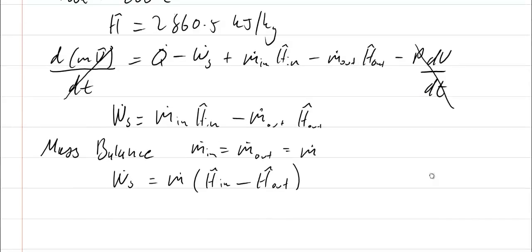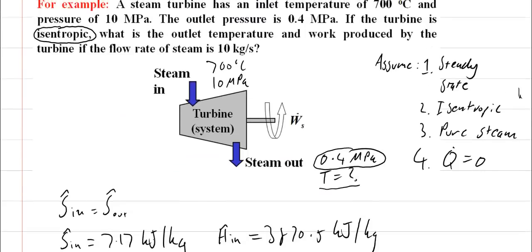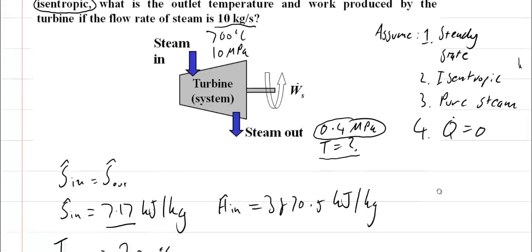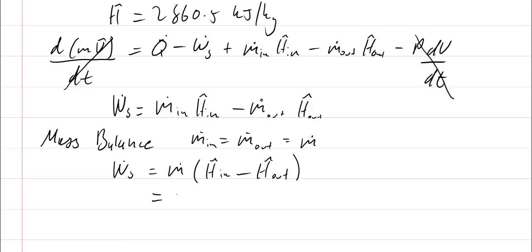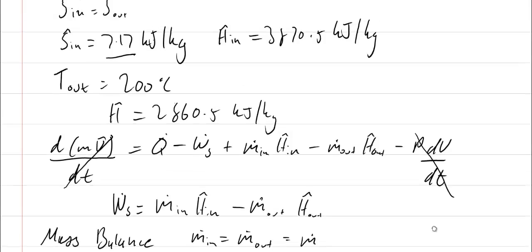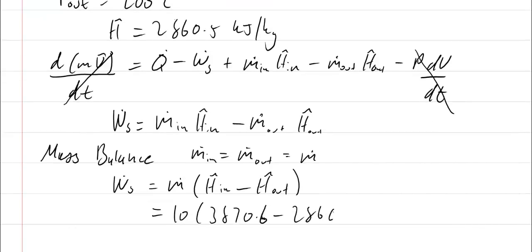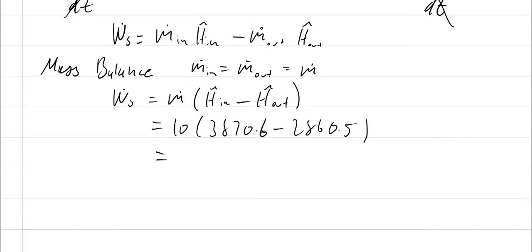I know what those H values are and I also know what my mass flow is. My mass flow is 10 kilograms per second, so 10 times 3870.6 minus 2860.5. Taking these away from each other gives ten thousand one hundred kilojoules per second, and that's equal to a 10.1 megawatt turbine.